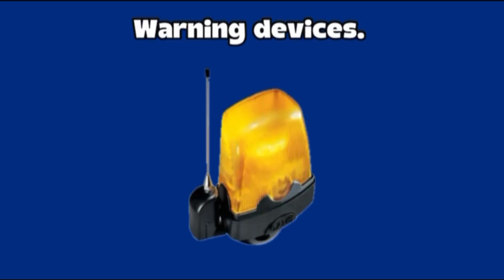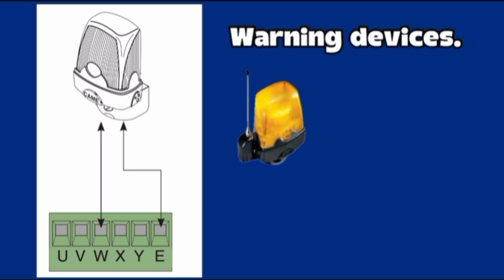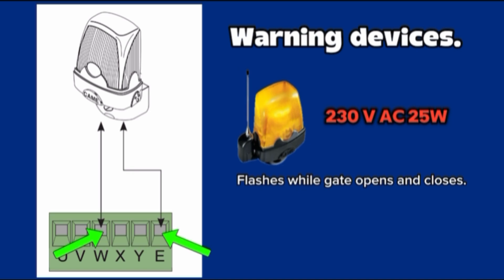Warning devices. Flashing lights should be 230 volt AC and 25 watt maximum. Flashes while gate opens and closes. Terminal E and Terminal W.